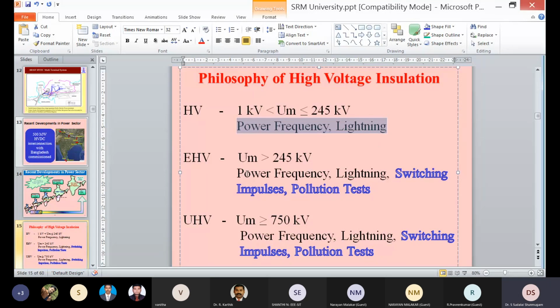When the extra high voltage comes into the picture, that is greater than 245 kV, we are considering switching impulse as well as pollution test. When it comes to greater than 750 kV, your switching impulse voltage per unit level and lightning impulse per unit level will be very close to each other, whereas the pollution test takes the predominant hand.